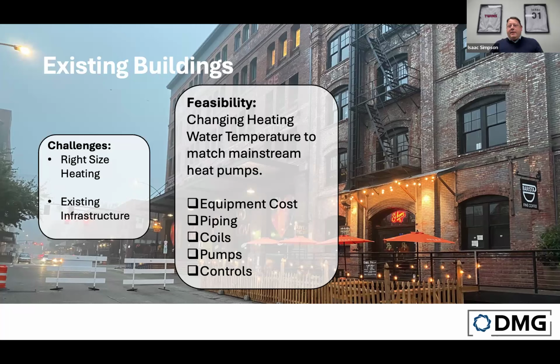After that, we have to figure out the infrastructure. There's a cost to the equipment, but then what are we connecting to? What piping, coils, pumps, and other control points exist in the building that might have to change if we went with a conventional heat pump versus a CO2 heat pump? If the system was designed to deliver 180 degrees to all the terminal units and coils, the first question is: could we turn that heat down a little and operate more efficiently?